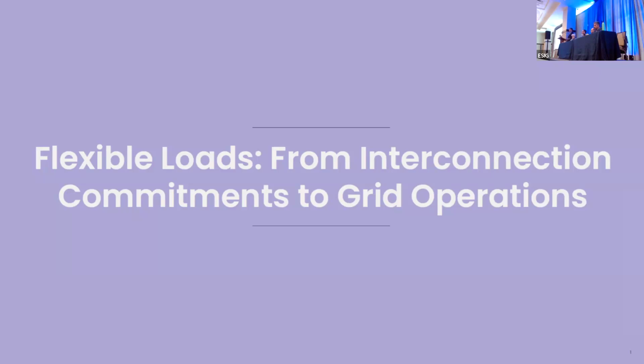When you add those things up, you end up with some amount of the nameplate interconnect to the grid that is functionally not available for compute. So if you had a hypothetical 100 megawatt connection with a historic data center design, you might get 65 to 75 megawatts, depending on the exact design, of available compute.